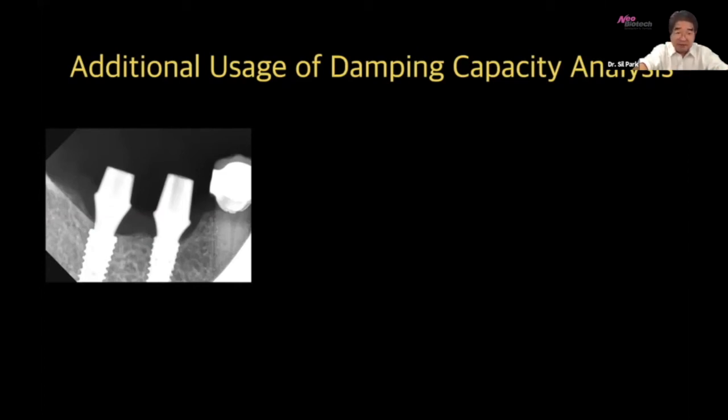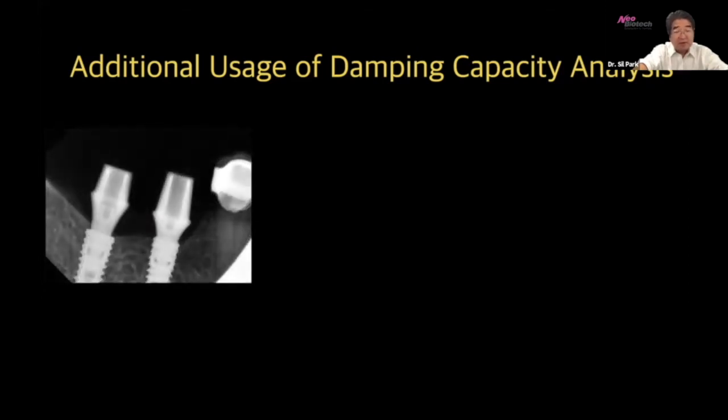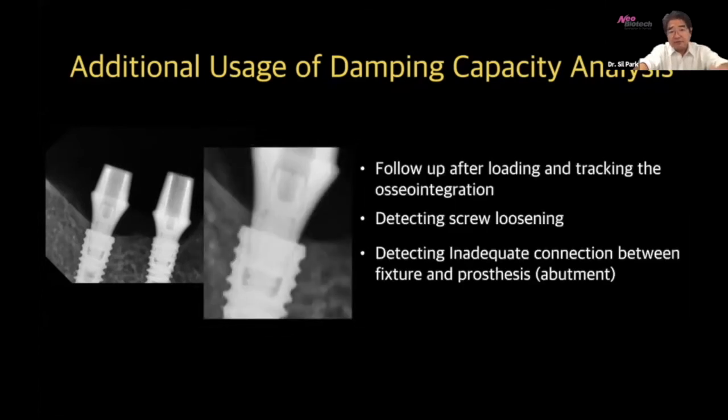What really happened is when I placed those stock abutments, as you can see over here, the stock abutment was not really tightened up, not well connected. In this situation, once you place those abutments, you can use the AnyCheck and check the stability. As you can see, if you have a crown screw loosening or the connection is not correct, it will tell you exactly and immediately that your connection is not really great, because your AnyCheck value is dropped.